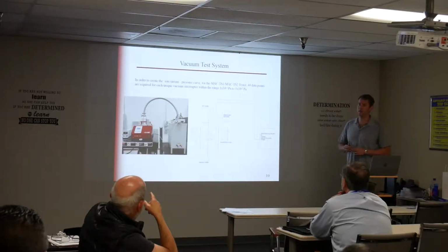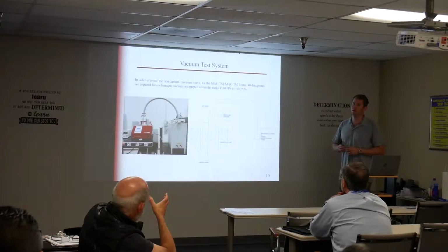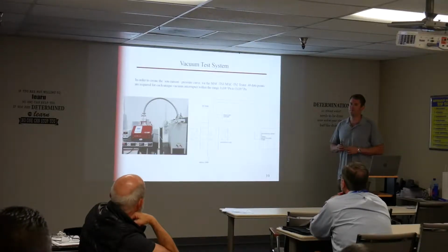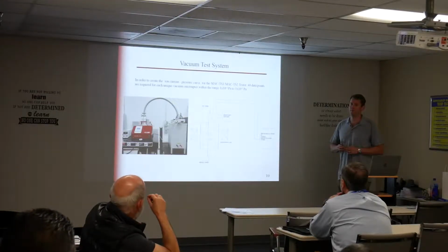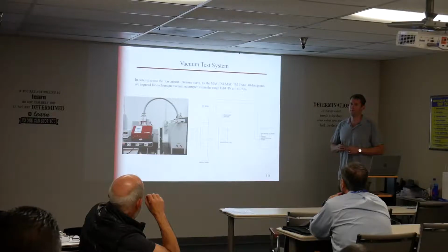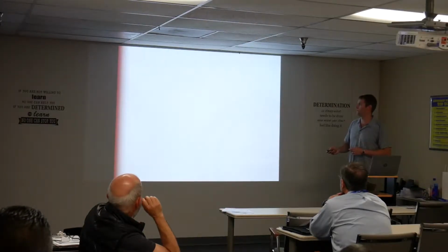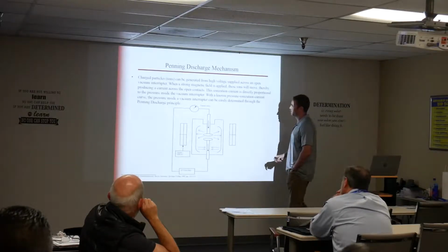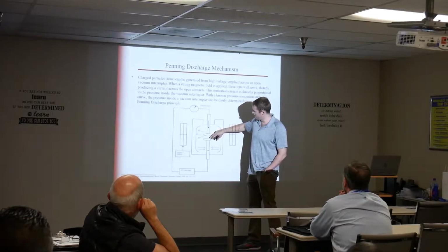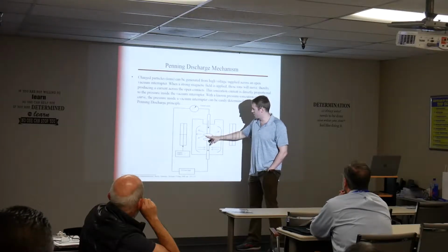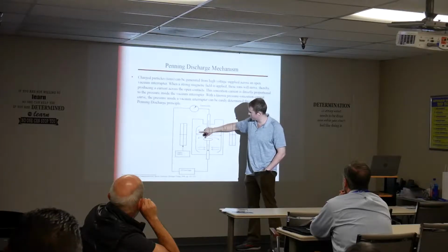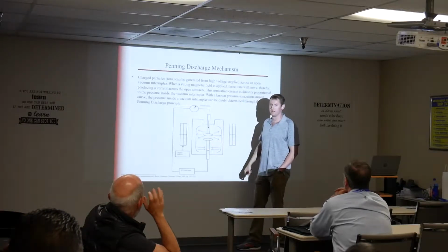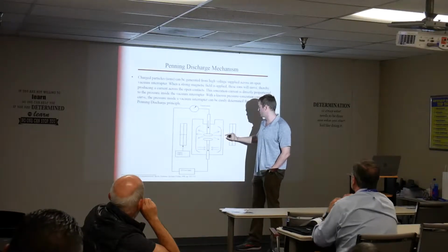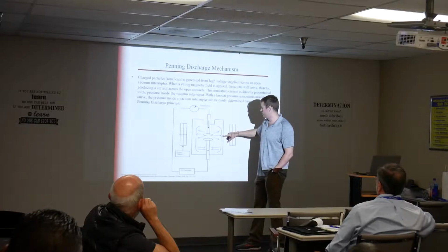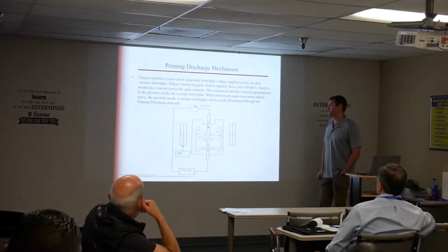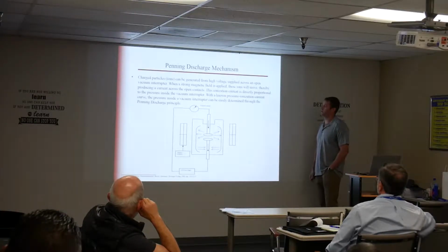I was wondering, you measure the current with a magnetic field to force the ions to move. Could you also do it by having the contacts closed and then doing whatever it should take to make them open and measure the duration of the flash? Some people do this test with it closed, because we're not just forcing them across this contact gap, we're also forcing them to that shield and then around that shield. But I have seen it where you have done this test with it closed and then attach the other one to the shield. But this is how we do it. But it's definitely possible to do it with the contacts closed.